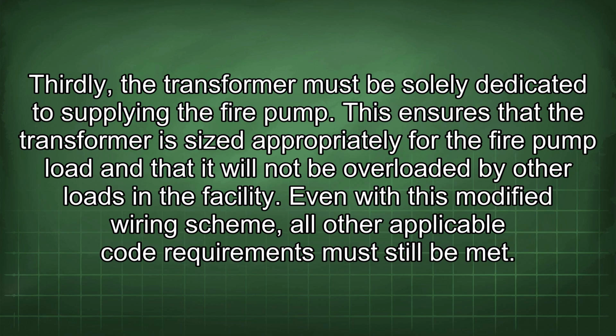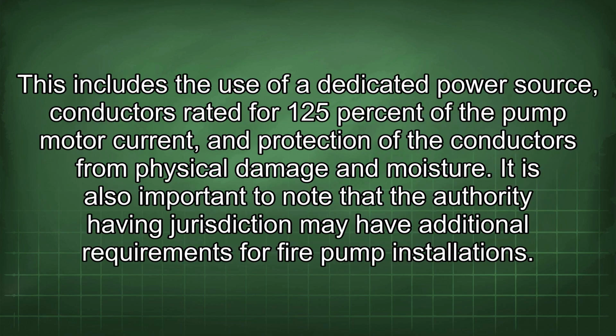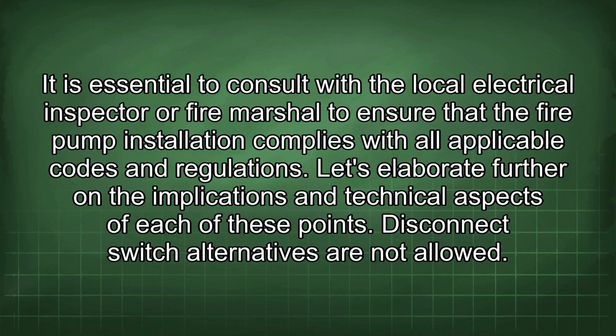Even with this modified wiring scheme, all other applicable code requirements must still be met. This includes the use of a dedicated power source, conductors rated for 125% of the pump motor current, and protection of the conductors from physical damage and moisture. It is also important to note that the authority having jurisdiction may have additional requirements for fire pump installations. It is essential to consult with the local electrical inspector or fire marshal to ensure that the fire pump installation complies with all applicable codes and regulations.